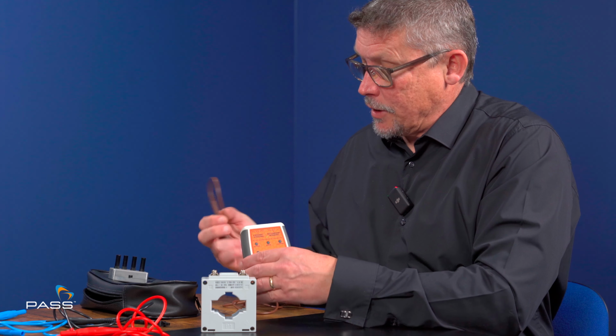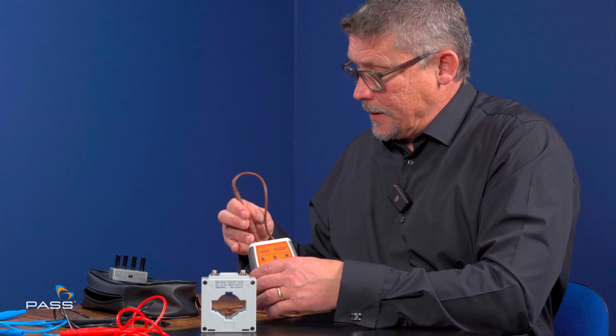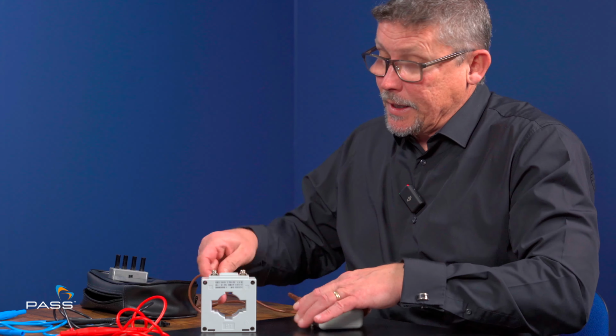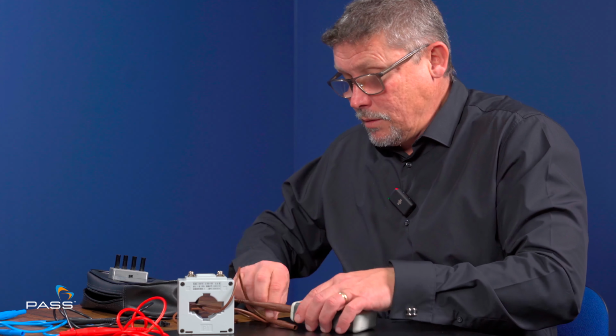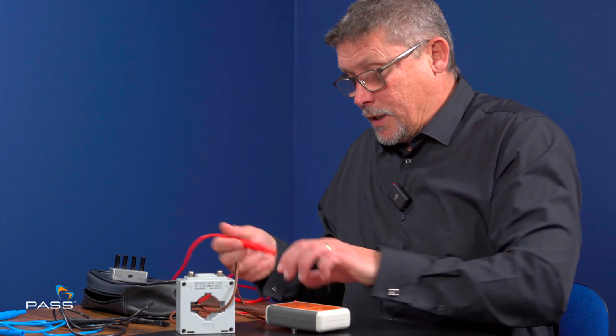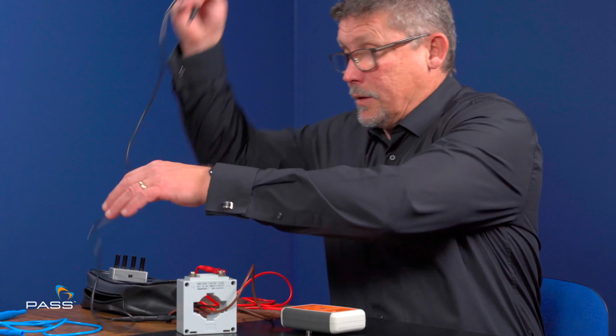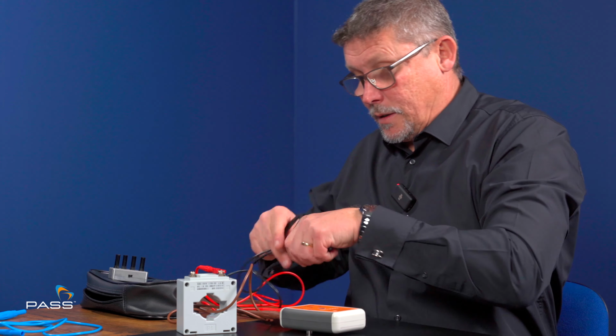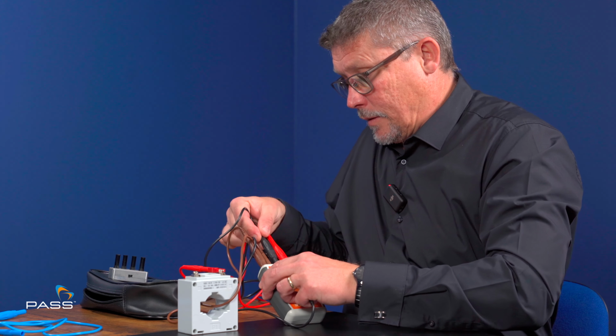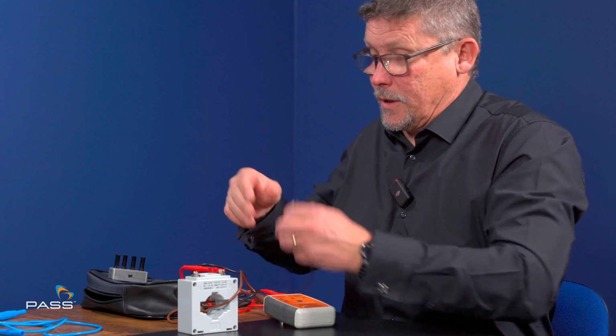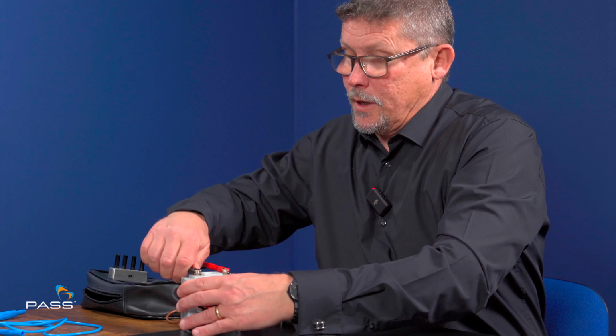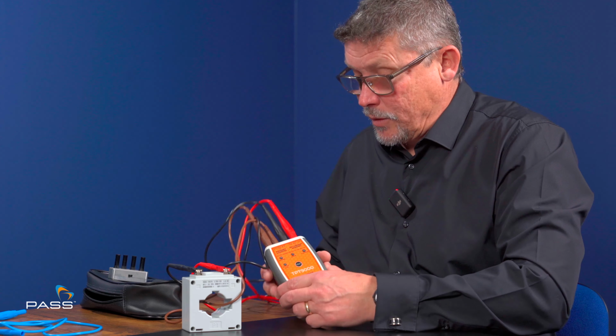So what we have here is the primary side and the secondary side. We'll randomly feed this through the CT - I haven't paid any attention to which way round that CT should go. I can pop that into there. We take our secondary positive, put it onto here, and secondary negative, like so. We click that onto the output. So we're feeding a current through the primary and looking at how it comes back through the secondary.